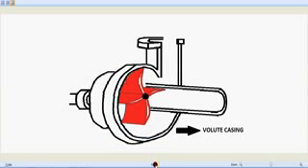And that's the volute casing. The significance of this casing is that you can see the area increases gradually from the top to bottom. As you can see at the top, at this area we have less area gap between the casing and the impeller, but as it slowly comes down, the area increases as shown here in the yellow shade.